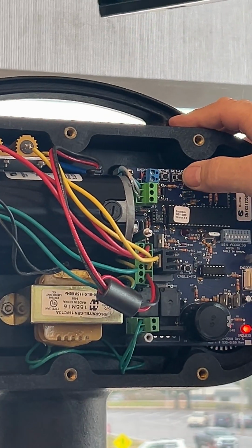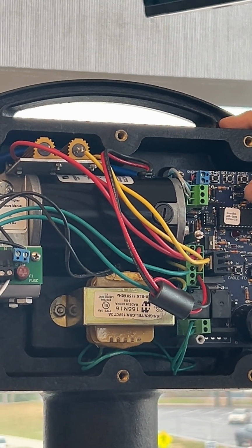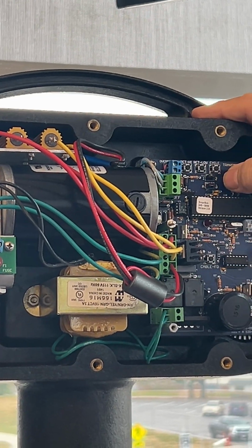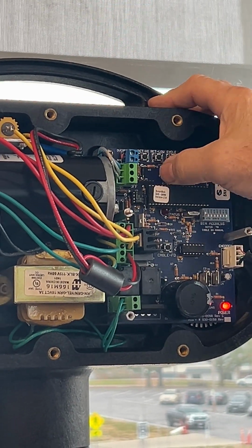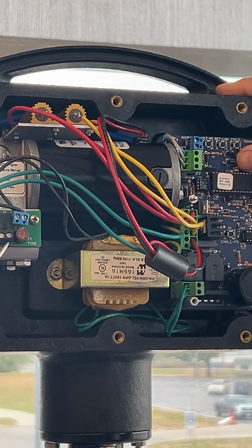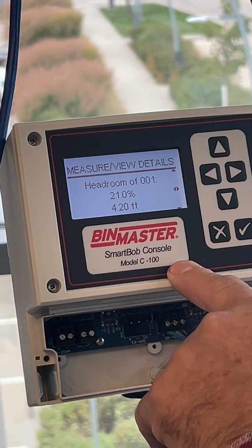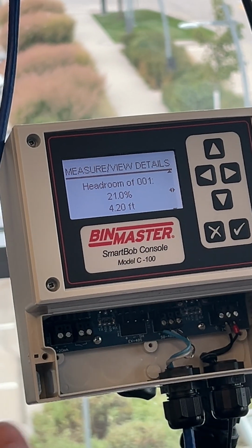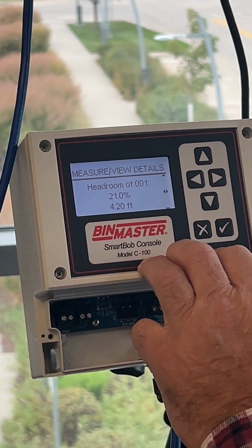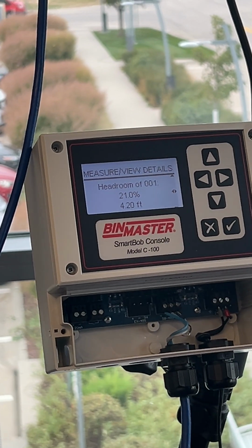So every SmartBob on your network has to work in the same protocol. So if you have some old ones that are B protocol only devices, then you would need to have it in a B protocol, or otherwise it's probably going to be in the A protocol. And it has to match the protocol that's called out in either your console or if it's our inventory program or whatever. They've got to be in the same protocol.